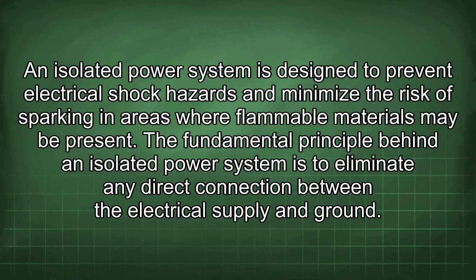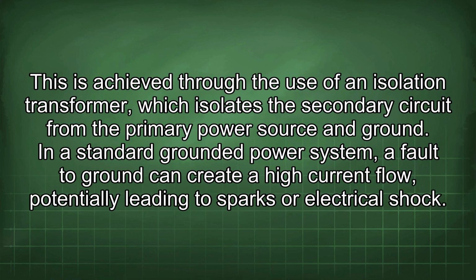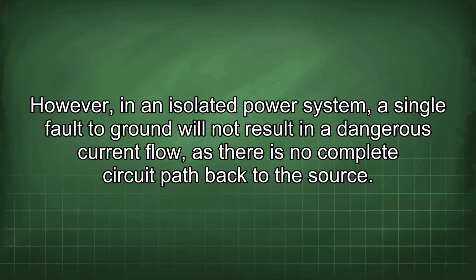An isolated power system is designed to prevent electrical shock hazards and minimize the risk of sparking in areas where flammable materials may be present. The fundamental principle behind an isolated power system is to eliminate any direct connection between the electrical supply and ground. This is achieved through the use of an isolation transformer, which isolates the secondary circuit from the primary power source and ground. In a standard grounded power system, a fault to ground can create a high current flow, potentially leading to sparks or electrical shock. However, in an isolated power system, a single fault to ground will not result in a dangerous current flow, as there is no complete circuit path back to the source.